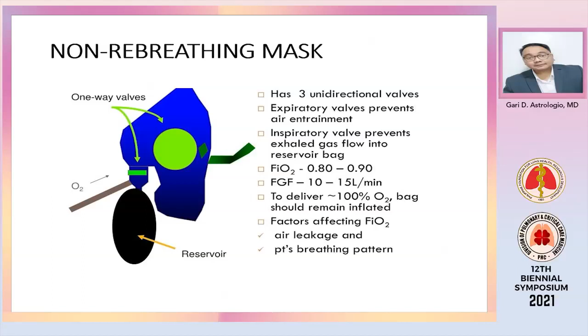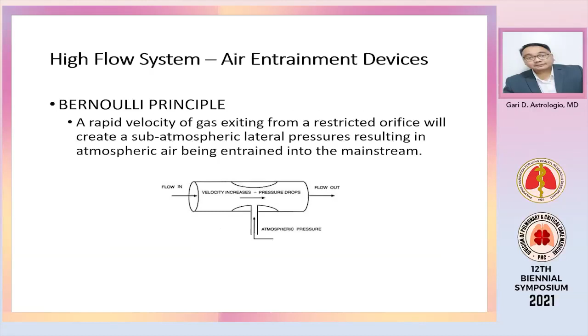Let us now discuss high flow systems, the air entrainment devices, whose mechanism is based on Bernoulli's principle, wherein a rapid velocity of gas exiting a small orifice creates a subatmospheric lateral pressure, and this results in the entrainment of atmospheric air, which is then combined into the mainstream. So the amount of air entrained varies directly with the size of the port of the device and the velocity of the O2 at the jet.